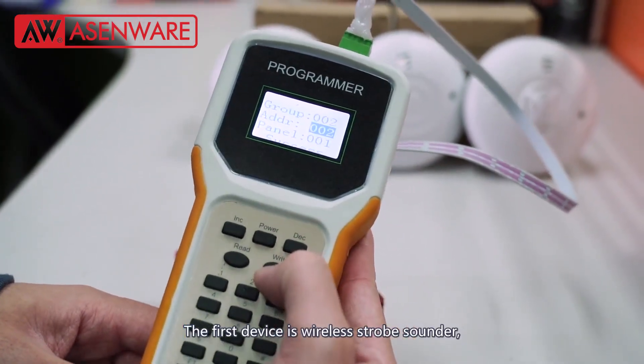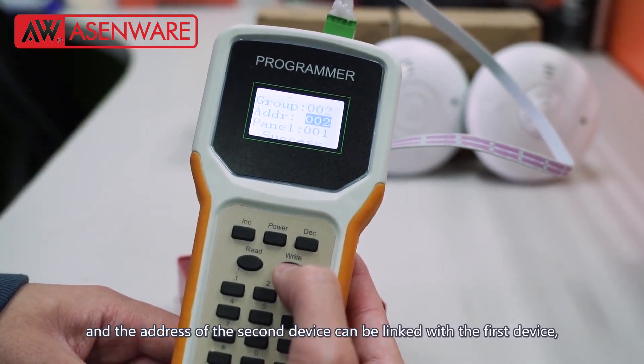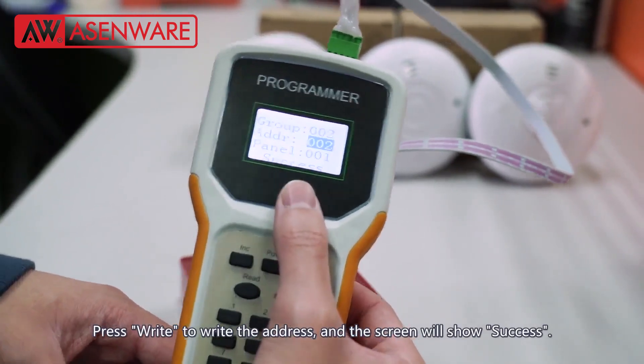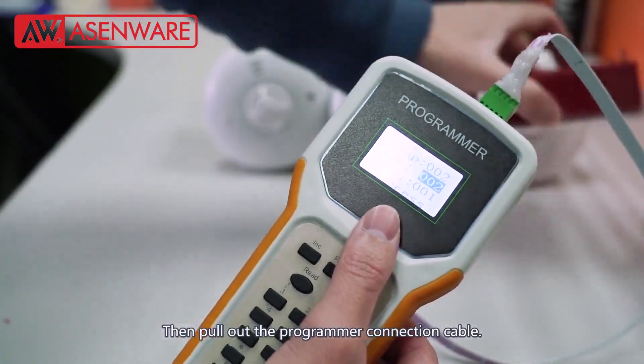The first device is wireless strobe sounder and the address of the second device can be linked with the first device. So the address of the manual call point can still choose address 002. Press write to write the address and the screen will show success. Then pull out the programmer connection cable.